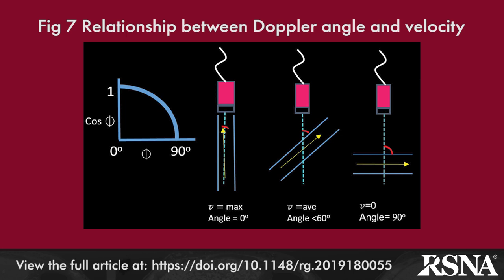Increasing the gain setting until color is visible outside the boundaries of the vessel, then decreasing gain until all the color specks outside the vessel wall disappear, ensures proper adjustment. Other issues include a high wall filter setting resulting in loss of diastolic flow. Low filter settings can ensure display of low amplitude velocities. Similarly, if the velocity scale is set too high, slow flow may not be detected on color or spectral Doppler. Artifactual absence of flow can be seen when the angle of inclination of the ultrasound beam to the vessel is at 90 degrees. Remember that the Doppler frequency shift equation includes the cosine of the angle between the beam and vessel, and that the cosine of 90 degrees is zero.